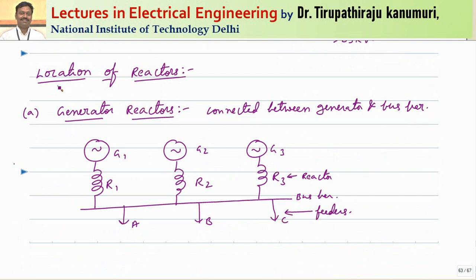Now, where should these reactors be placed? Depending on the location, different types of reactor arrangements exist. The first is called generator reactors, where the reactor is connected between the generator and the bus bar. In this arrangement, the reactor continuously carries the rated current from the generator to the bus bar, resulting in continuous voltage drop and power loss.